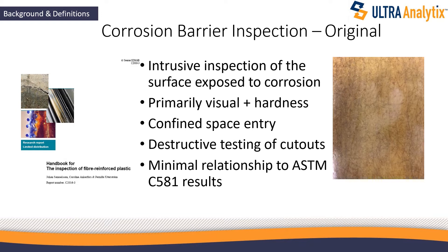Originally, corrosion barrier inspection was intrusive — it still is for the most part. What we do is go inside, say inside a storage tank, and ask: do we see any damage to the corrosion barrier? I'm showing a picture of a corrosion barrier here. We take a look at the color and say, does it seem to fit with an undamaged state of the resin? How hard is the surface? We measure that with something called a Barcol hardness tester. This always requires a confined space entry. We might take a cutout — cut a hole and place a nozzle in to repair it, which of course requires repair. There's almost no relationship of the results of this inspection to the ASTM C581 results.